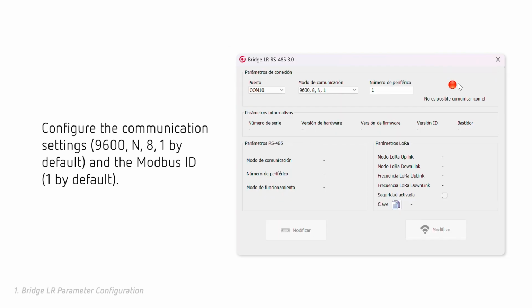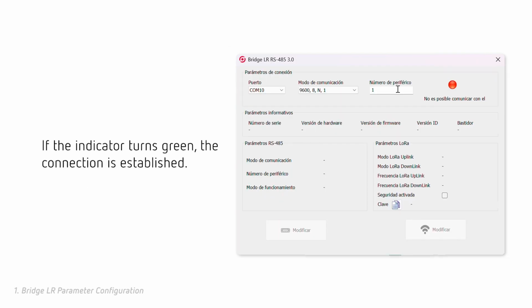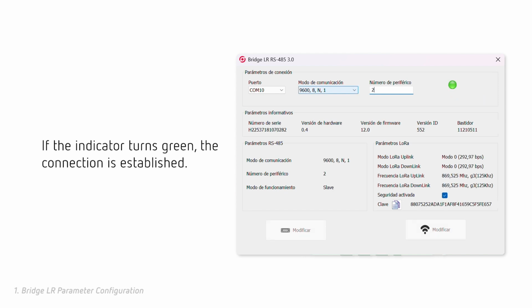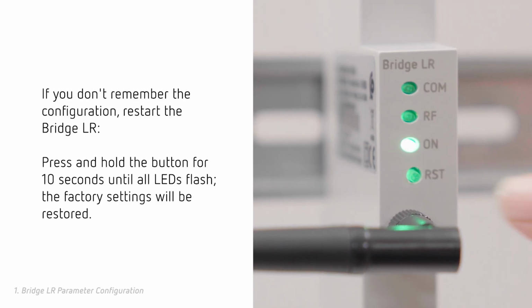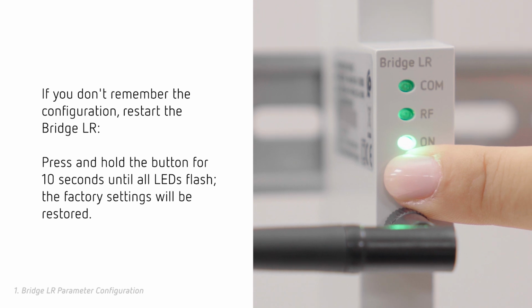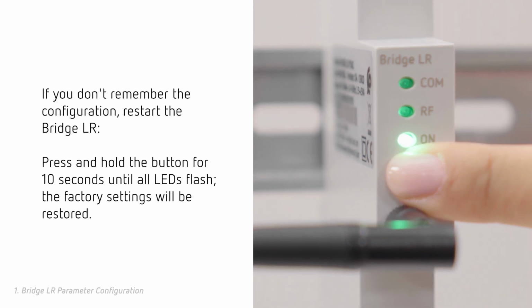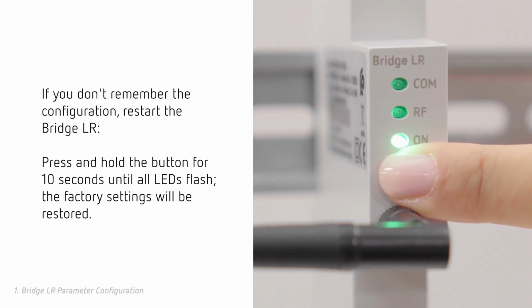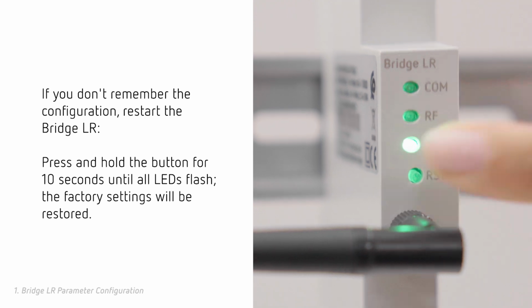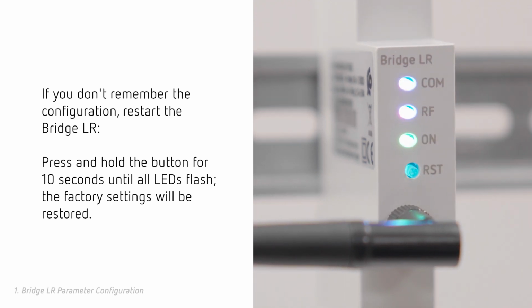Configure the communication and the Modbus ID. If the indicator turns green, there is a connection. If you don't remember the configuration, restart the bridge LR. Hold down the button for 10 seconds until all the LEDs start flashing. The factory settings will be restored.